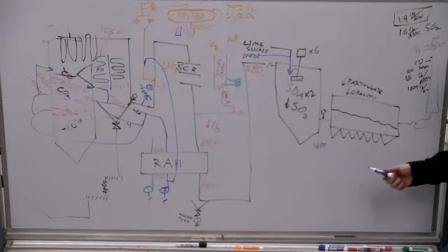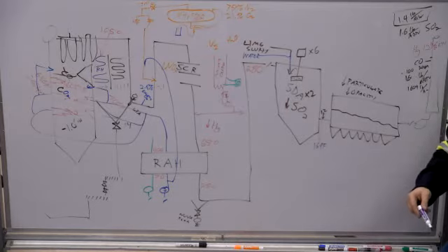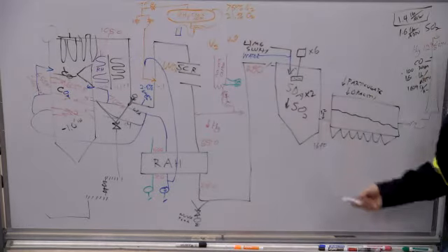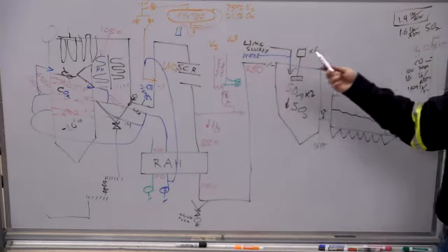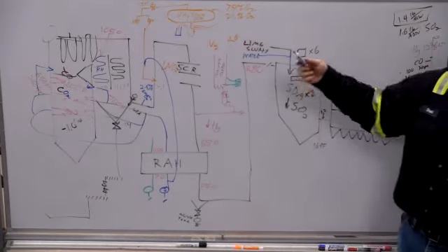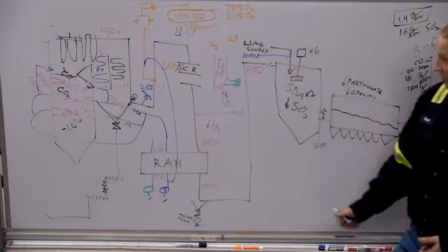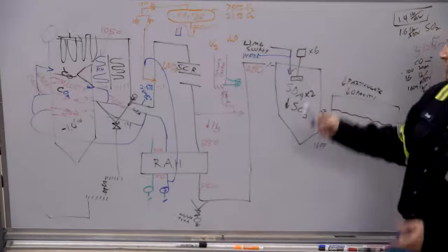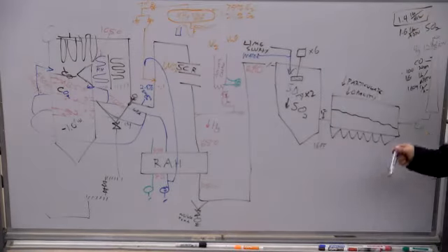Now there's something funny that happens, which is the south SDA tends to run way hotter on the inlet temperature than the north SDA. Alpha tends to be like 270 on the inlet, and Bravo tends to be like 290, 300 on the inlet. Both those temperatures are higher in the summer. Let me finish talking about the SDAs. I'll come back to that.